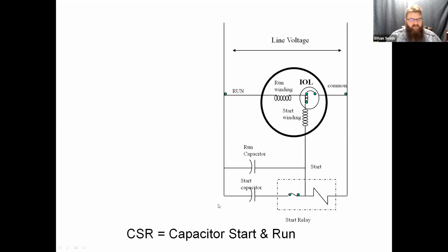So this mystifies a lot of guys out in the field because you got this magic black box. Well, that's all that magic black box is, it's just a coil and a set of contacts. The trick is these are normally closed contacts. So when the motor's disengaged, that winding isn't energized, and so these are in circuit with the start capacitor. Once the motor starts to spin and we get back EMF, those contacts are going to open up and drop that start capacitor out.